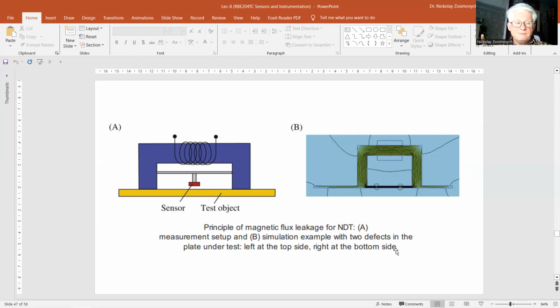But you should note that the defects create field lines perpendicular to the surface, so sensing in this direction is recommended. With a sensitive magnetic sensor, it is possible to detect defects in the order of micrometers, and even defects at the bottom side of relatively thin plates or pipe walls, say several millimeters thick.